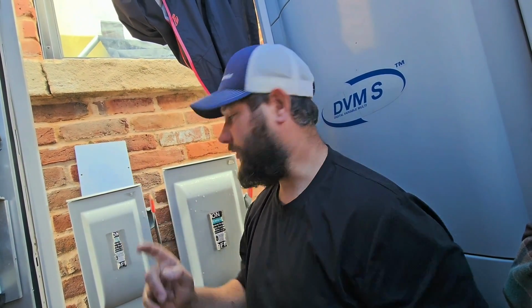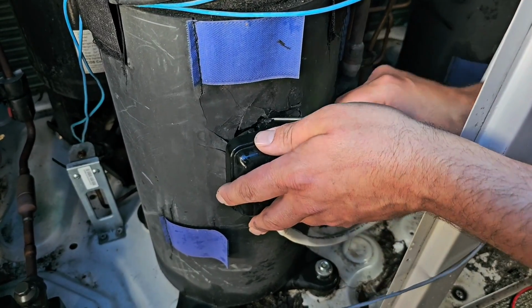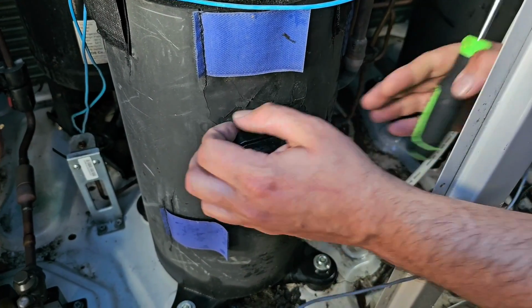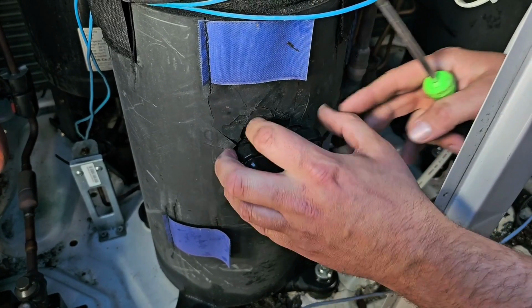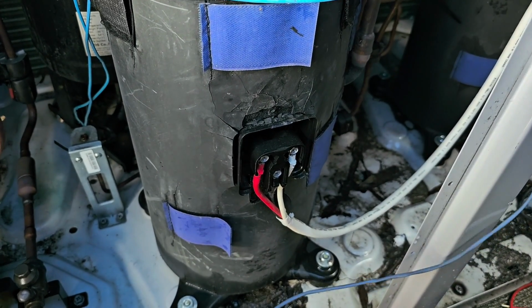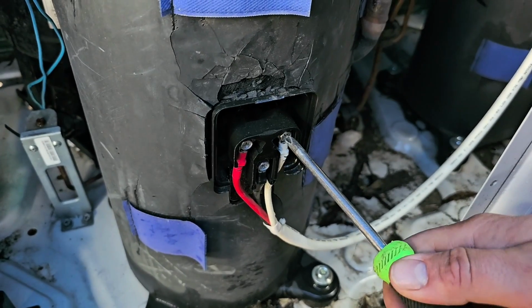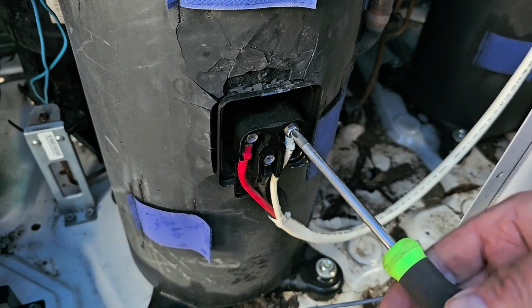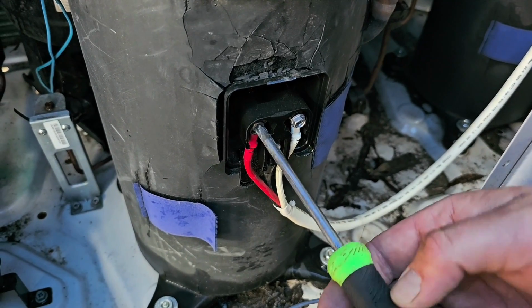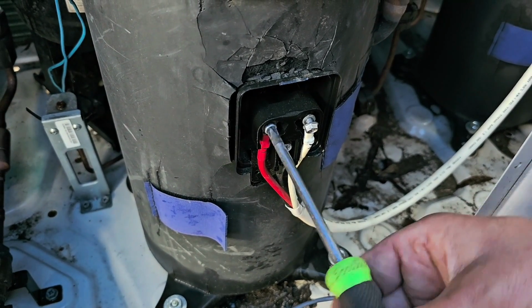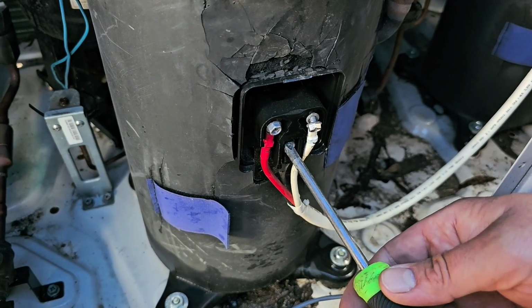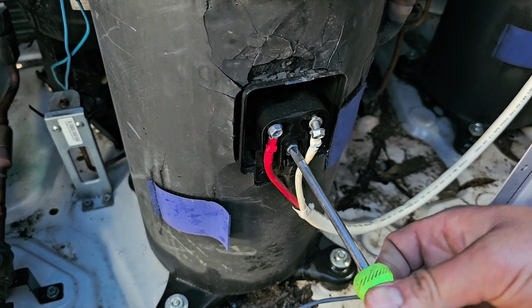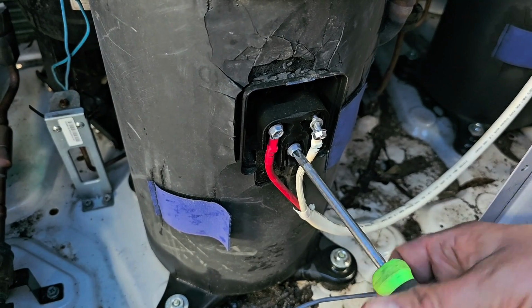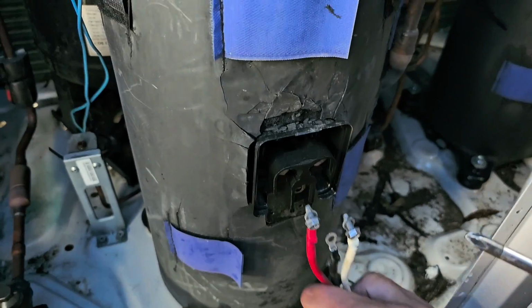So what we're going to do now is turn the disconnect off, and I'm going to show you how to take the covers off and check the compressor windings. Now let's take the covers off of the compressors while we've got the disconnect off. Make sure there's no power, and make sure you've waited at least 15 minutes after disconnecting power to even mess with the wiring. So I've got these 3 wires, and I'm going to use a Phillips screwdriver to loosen up the terminals. 1, 2, and 3. And then once that's off, make sure you don't lose the screws.